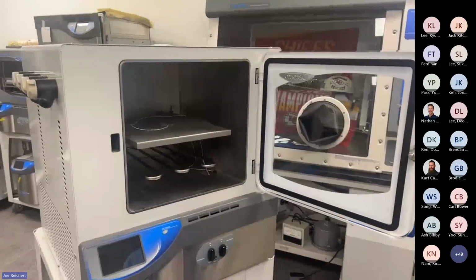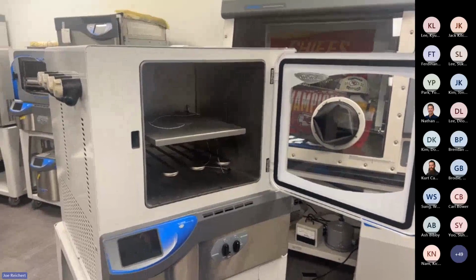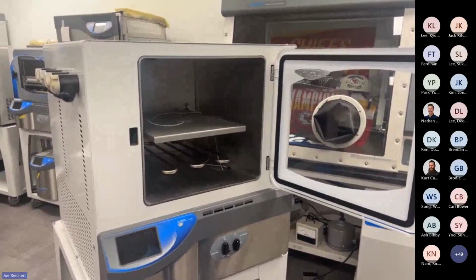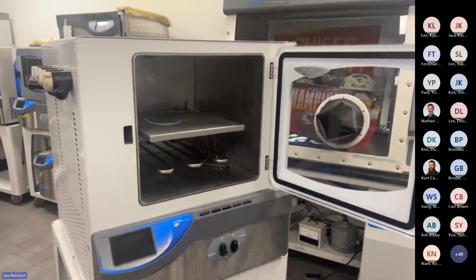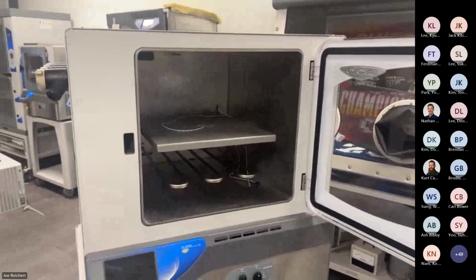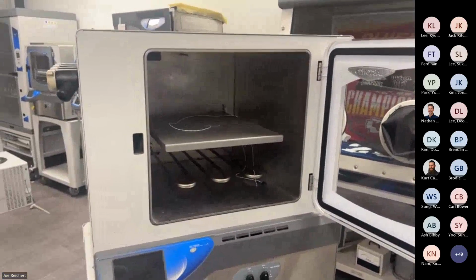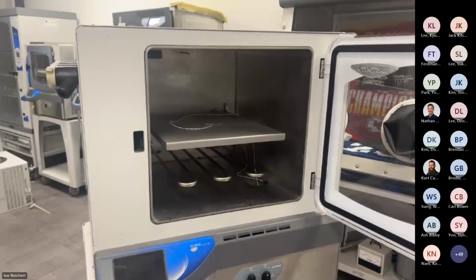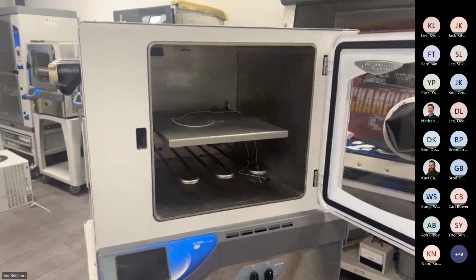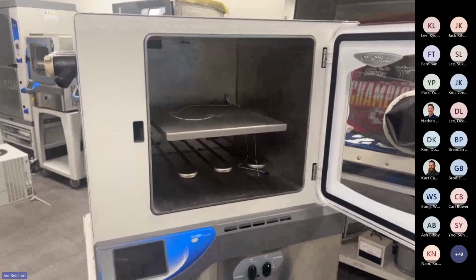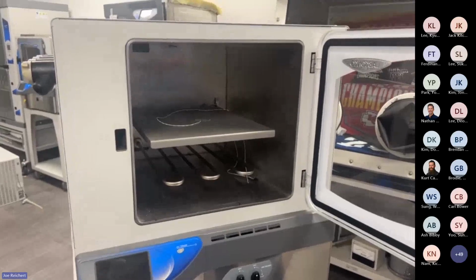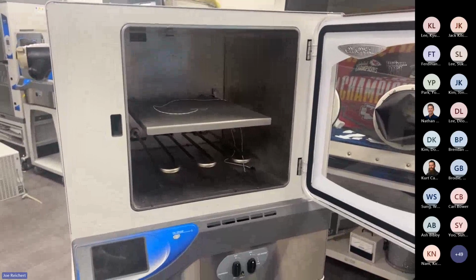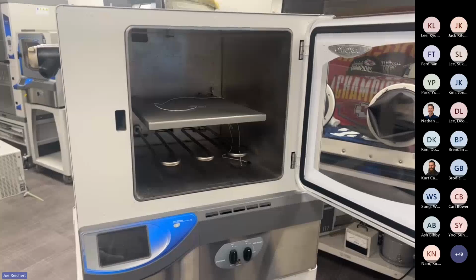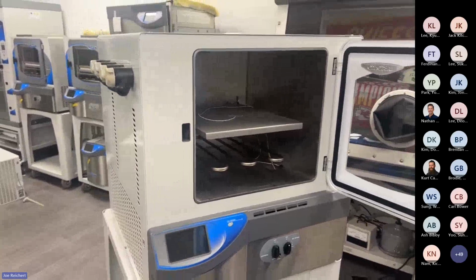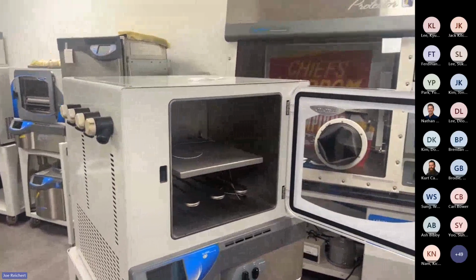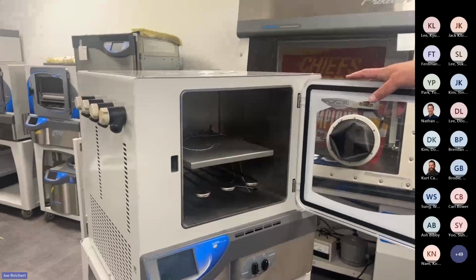And what that sensor does is it's going to be the temperature that the display takes its reading from whenever it's in max cold mode. So in max cold, it only uses that temperature sensor. When you're in any other mode on the unit, it uses a different sensor that's on the back of the unit that we'll see here in a little bit when we take it apart. But that one is on the Lexol line, just to the left of the heater.